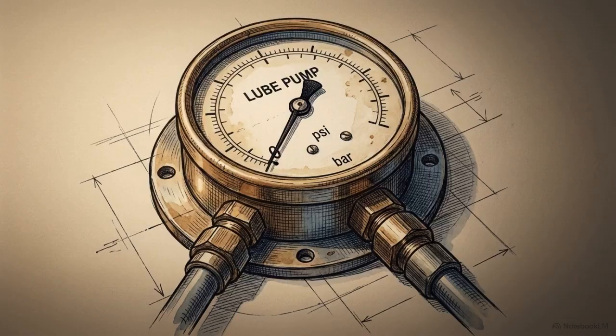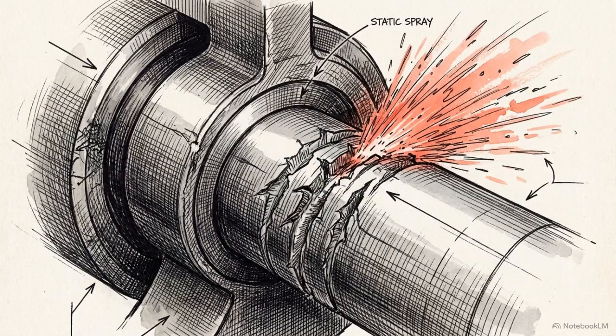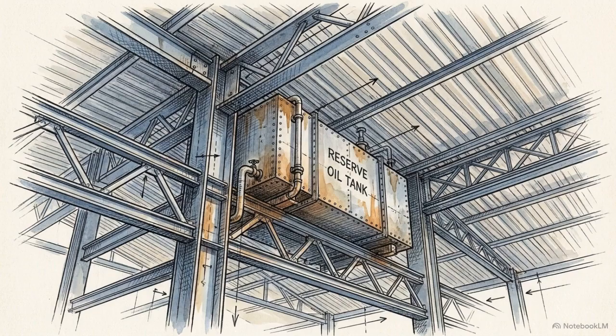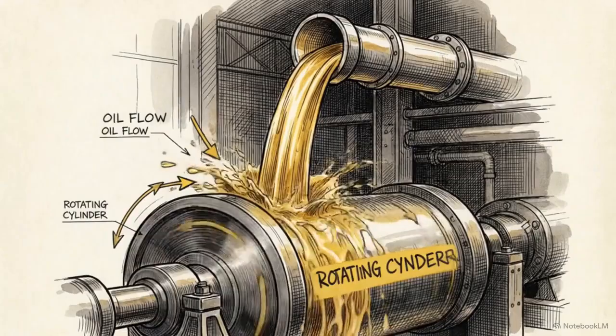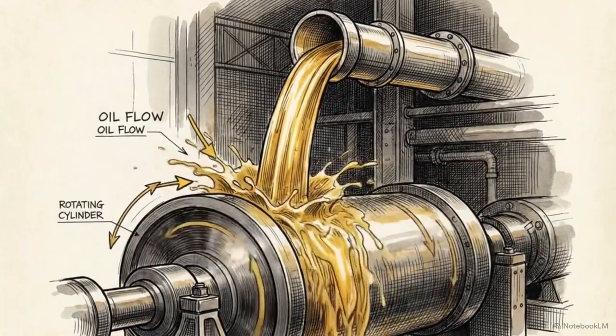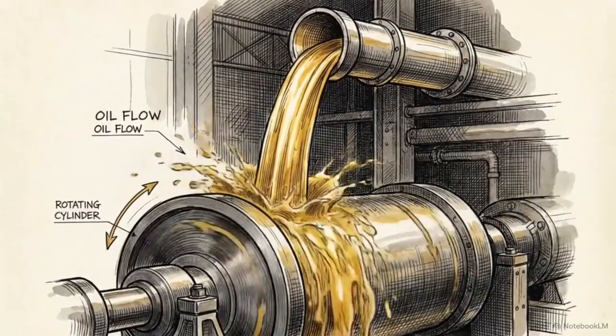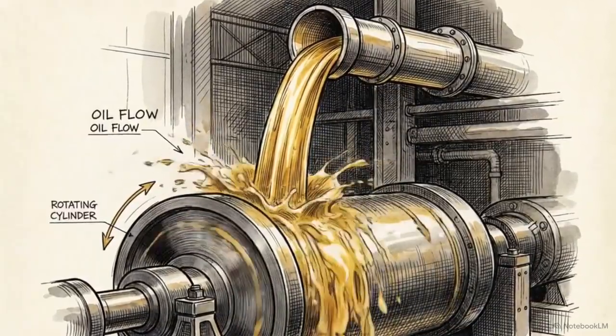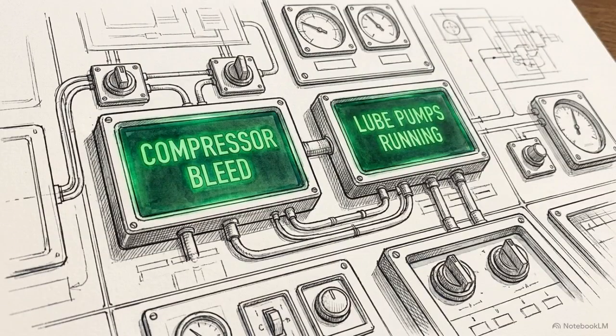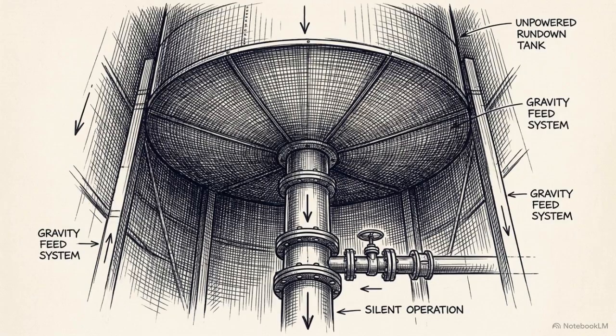Consider the consequences of a total plant AC power blackout while the massive generator is spinning at 3,600 RPM. In a blackout, the auxiliary lube pumps die instantly. Without intervention, a coasting rotor weighing several tons would score its own bearings and seize within seconds. To prevent this, the package includes overhead rundown tanks. These use pure gravity to dump stored oil into the bearings, ensuring the rotor stays lubricated until it reaches a full stop. At full load, active pneumatic pressure and high-temperature synthetic chemistry maintain the engine's internal boundaries. But in a total systemic collapse, gravity is the only failsafe that protects the machine.